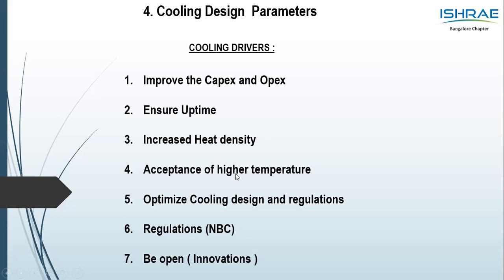Acceptance of higher temperature. We will look at the temperature in the next slide, but accepting very high temperature. Even today, most of the smaller server rooms say that if I am feeling cold, then I assume the servers are feeling cold. But the concept is not that I should feel cold. Maintaining the right temperature as per ASHRAE norms is very important for the server or rack. Optimize the cooling design and regulation, keeping a check on the building regulations of the National Building Code, and be open for innovation. Let's not go the traditional way of cooling. Let's look at innovation, what is new, so that you can bring down your operational cost.